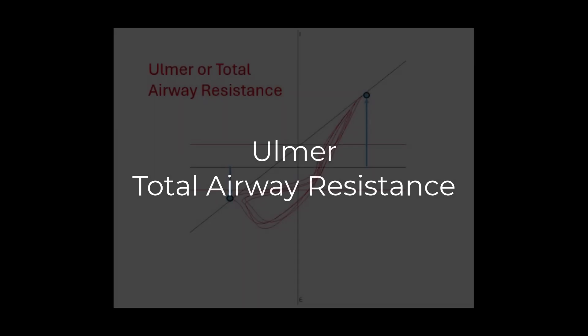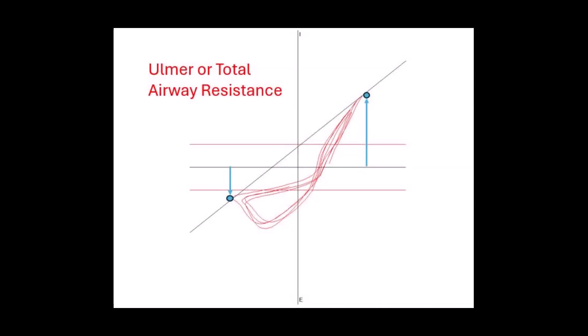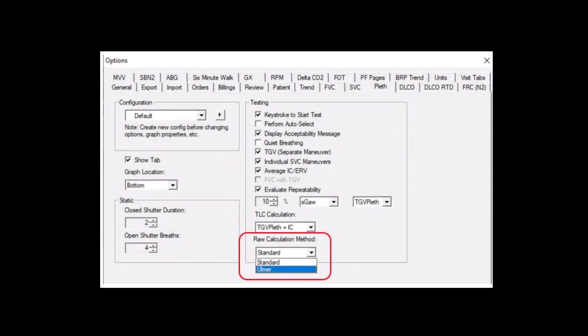Two other methods for adjusting the airway resistance loop may be seen outside of the United States. The first method is called the Ulmer method, sometimes called total airway resistance. The Ulmer method defines the line of best fit between the points of maximal inspiratory and expiratory volume shifts or pressure change. By adjusting the line of best fit to the maximal pressure change, you may have improved sensitivity at end expiration; however, you may also have increased variability. The Ulmer method can be set as your default for computer-generated line fit. While in the plethysmography test screen, go to the F5 options menu. Under raw calculation method, Ulmer can be selected from the drop-down menu.